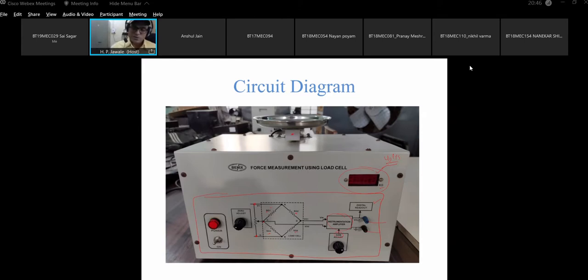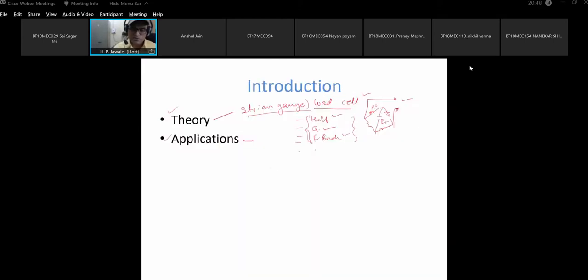So in actual practice, the load cell is something you can find in the textbook. This is nothing but a bar acting as a cantilever, and in between there is one recess, one slot provided like this, so that it has a minimum cross section at 4 different points. And then I'm going to paste strain gauge 1, strain gauge 2, and from the bottom side 3 and 4.